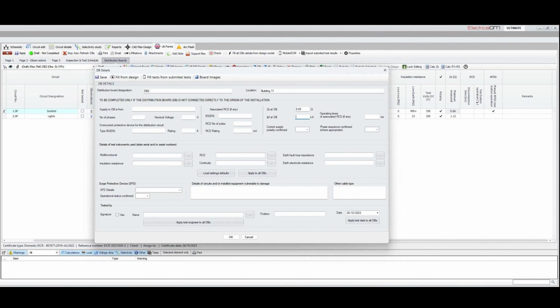And that's explained with the extra earthing conductor in the board and the fact it's a TN-S earthing arrangement, whatever the DNO tell us to assume as regards TN-C-S. So we're recording the 0.46, because that's Ze in this box. And again, there's no RCD. You can confirm the supply polarity. If there's phase sequence, you can confirm it in there.